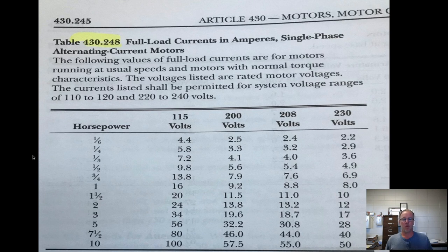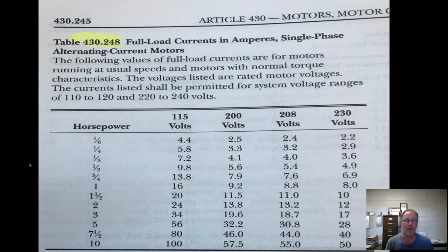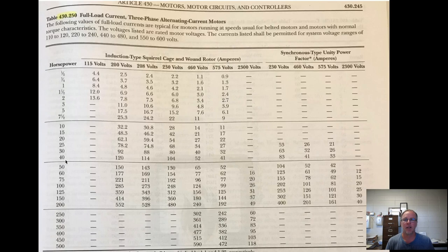Let's say we've got a one-horsepower motor at 115 volts — it's 16 amps. You go right to the table. It's real easy. You've got 115 volts, 200 volts (hardly ever used), 208 and 230. It goes up to 10 horsepower. This is the three-phase chart, Article 430-250.